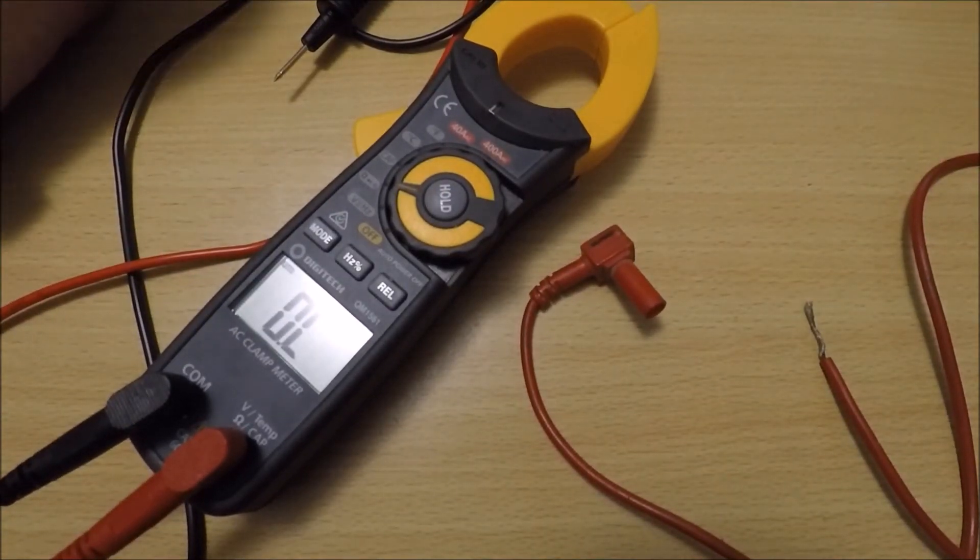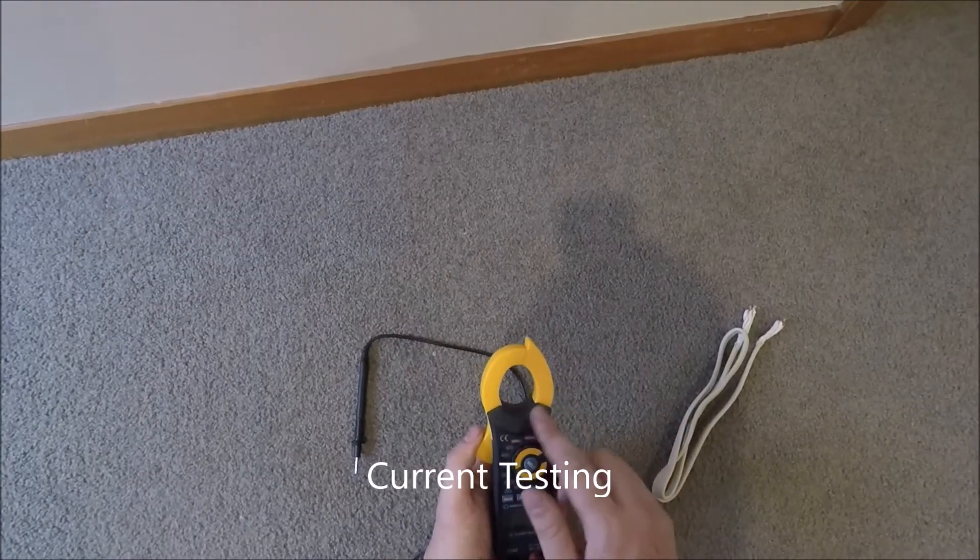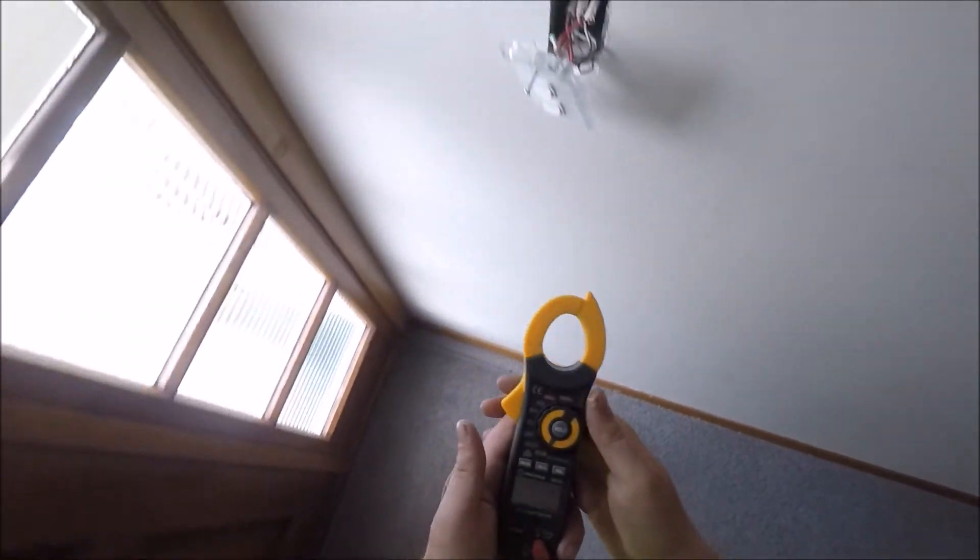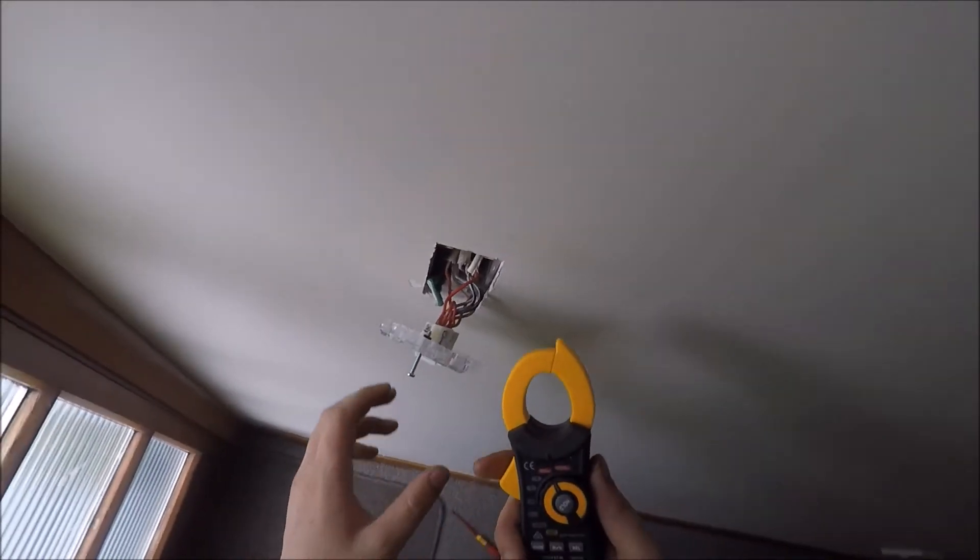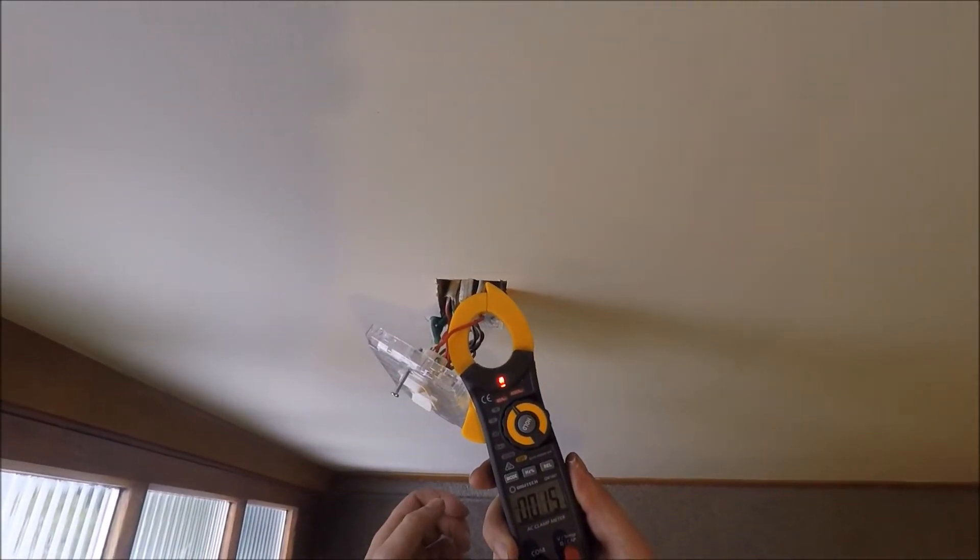I'm going to go through current now. I've turned the lights off so I hope you can see this. Since we're drawing low current, we're going to put it on the 40 amps AC rating and we're going to hook it around one of these cables that we want to make sure our load is drawing current. So we can flick the switch on and it comes up with 0.15 amps. So we can tell that this circuit is working because it's drawing current.